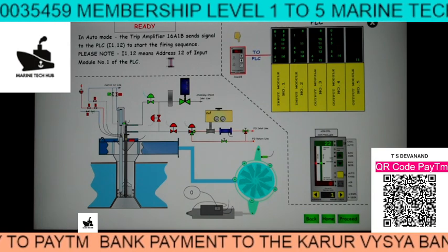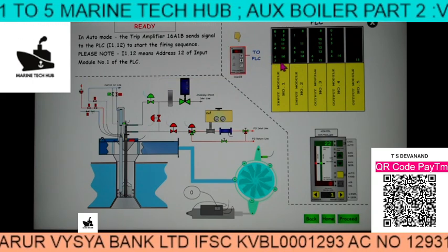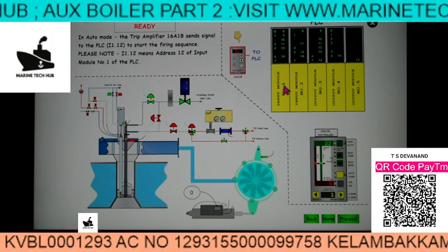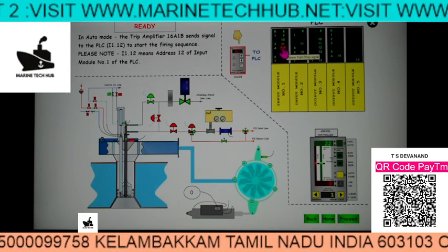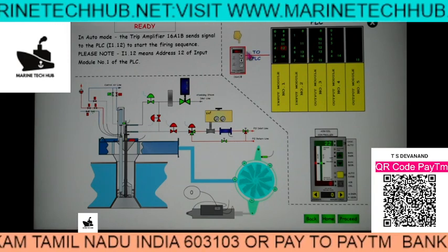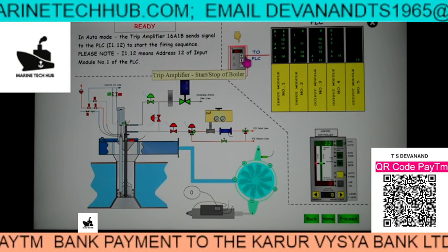To start the boiler we require the trip amplifier. This is the trip amplifier which is sending a signal to the PLC. The PLC has modules 1 to 5. Right now we are looking at module 1 and 1.12. This 1.12 is nothing but the burner start-stop signal. The first signal will go from the trip amplifier to the PLC.